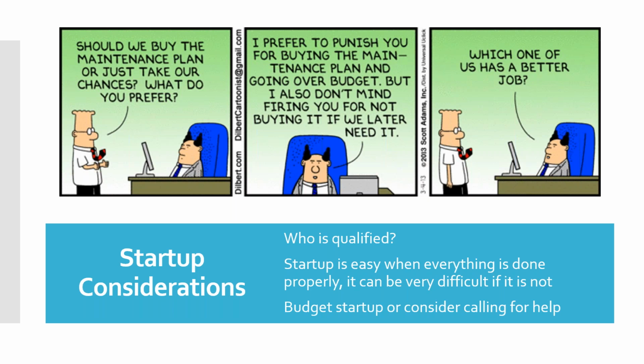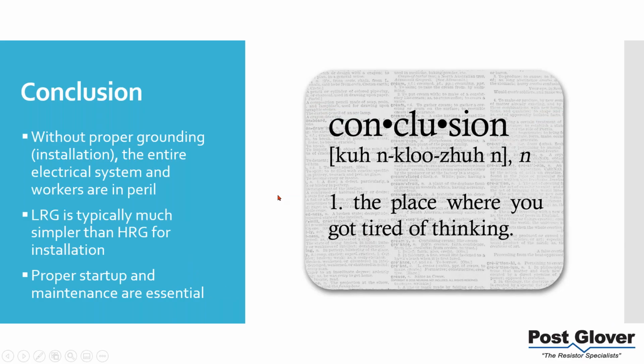The good news about the high resistance ground system is it can actually diagnose things with your system. So it can definitely be an issue with the HRG, but it can also be, for example, a solid ground system or something like that, or if you have an open neutral, etc.